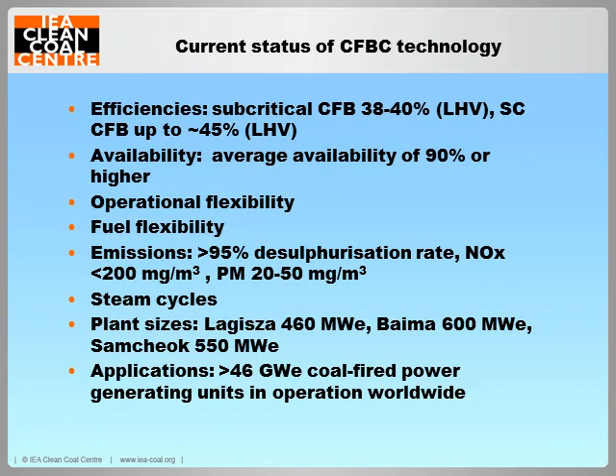CFBC boilers can achieve an average availability of 90% or higher. They can operate at base load or in a load following mode, but are not suited for on-off cycling. CFBC boilers are capable of burning all types of coals, coal waste, and a wide variety of bituminous biomass and waste-derived fuels, alternatively or simultaneously. A wide variety of opportunity fuels can be used almost interchangeably without major, if any, plant modifications.